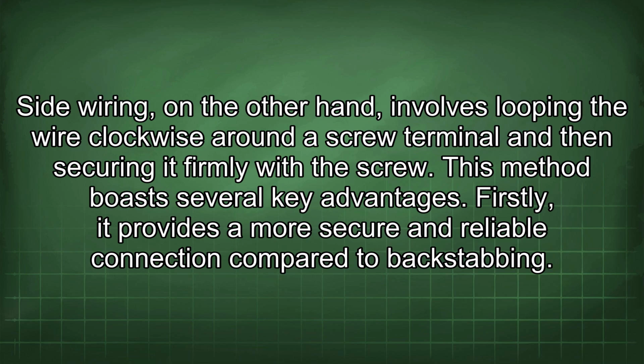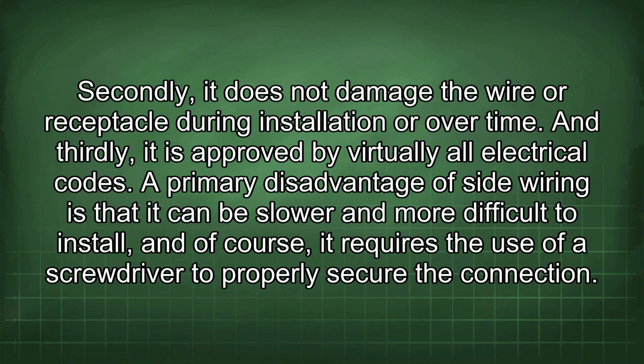This method boasts several key advantages. Firstly, it provides a more secure and reliable connection compared to backstabbing. Secondly, it does not damage the wire or receptacle during installation or over time. And thirdly, it is approved by virtually all electrical codes. A primary disadvantage of side wiring is that it can be slower and more difficult to install, and of course, it requires the use of a screwdriver to properly secure the connection.